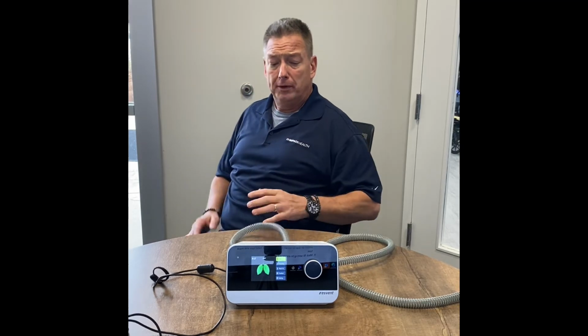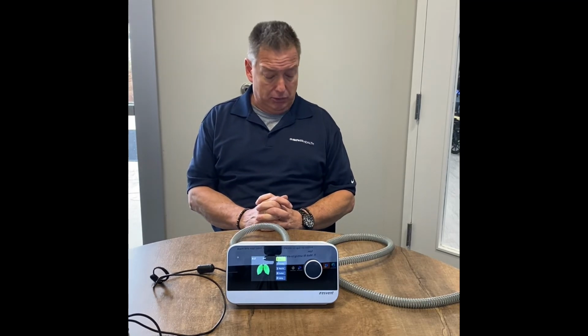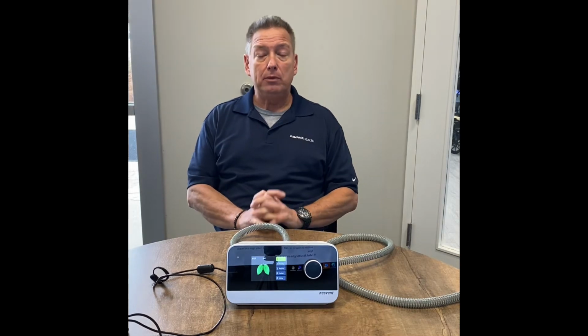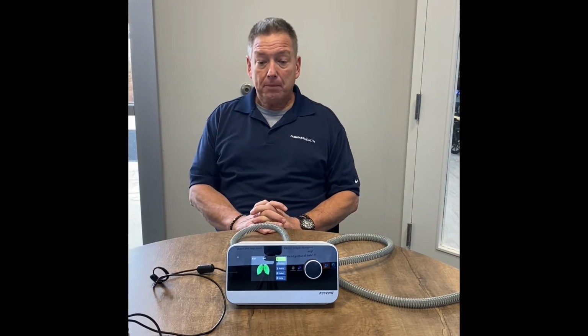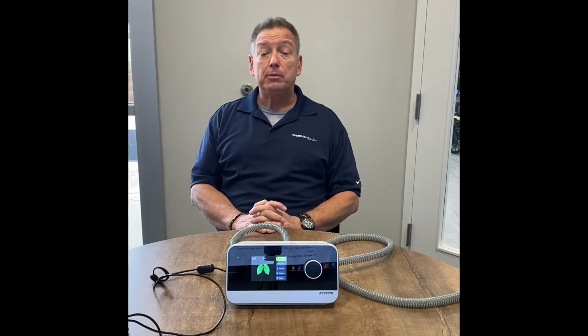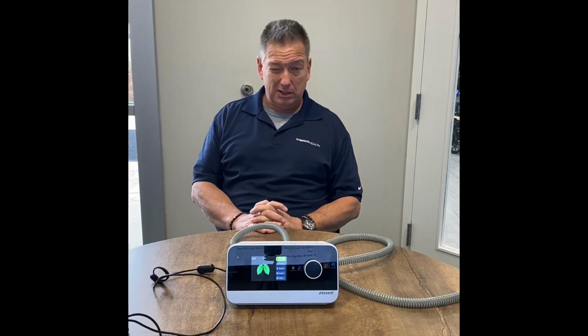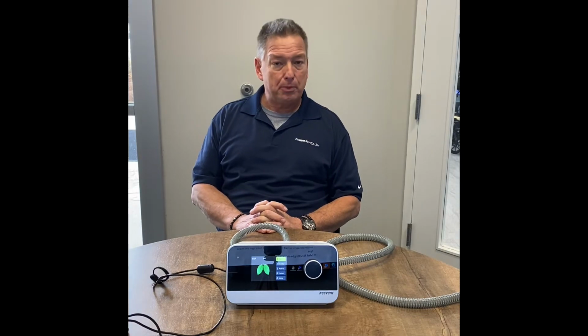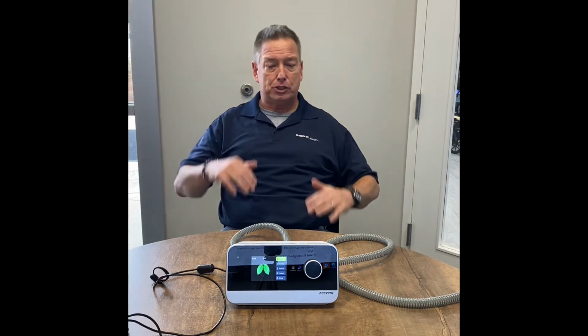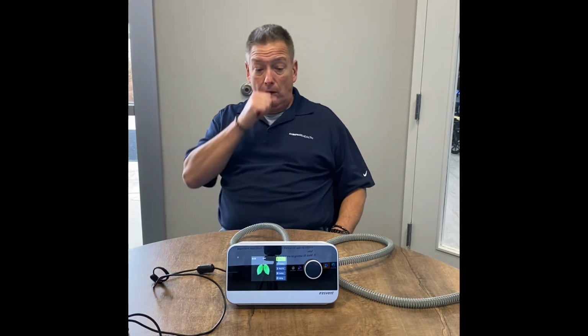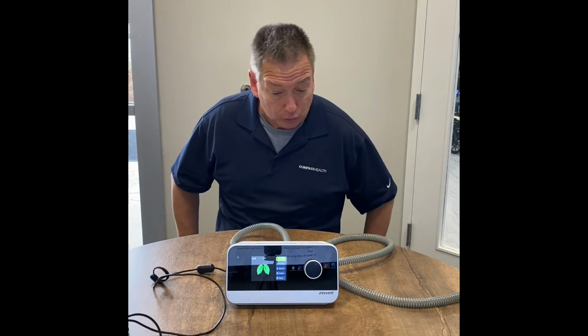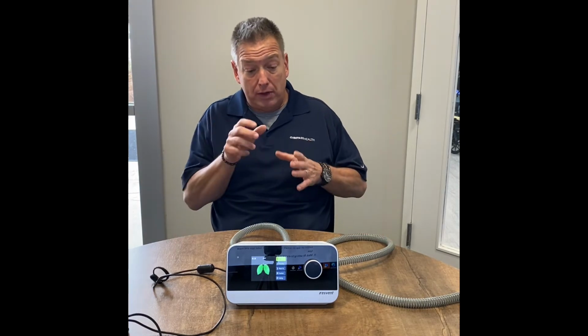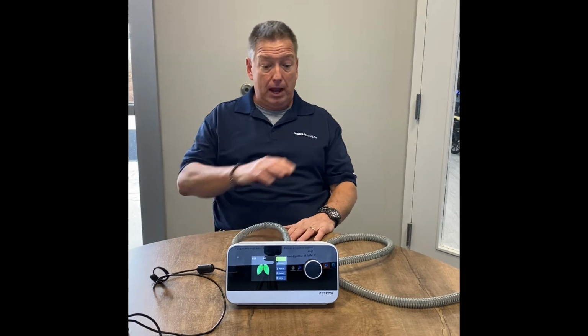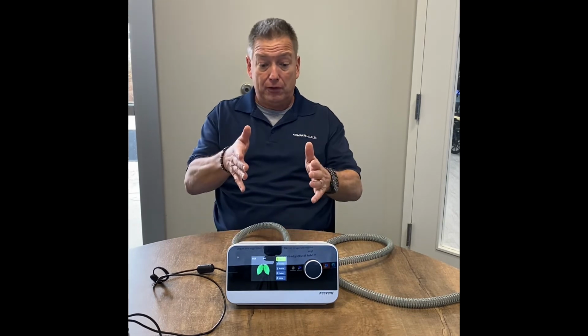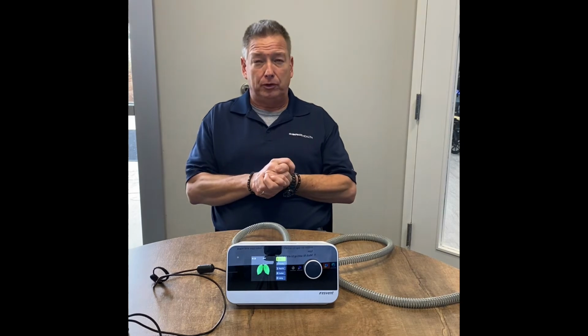So that's really cool. The ramp in here, the ramp adjustment, is extremely functional and does an amazing job. It's adjustable in increments from 5 minutes to 60 minutes. That's a pretty broad range. And of course, you have your starting pressure and your ending pressure, and you can adjust all that like most of them do. Excuse me, but the auto ramp is great. You just set the time you want in there, in your comfort settings, and boom, it functions perfectly and does exactly what you program it to do.